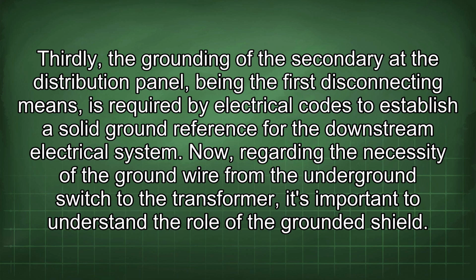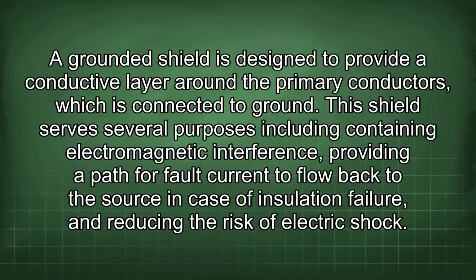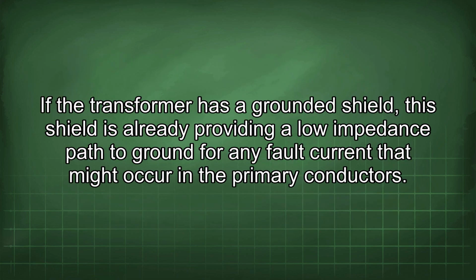Now, regarding the necessity of the ground wire from the underground switch to the transformer, it's important to understand the role of the grounded shield. A grounded shield is designed to provide a conductive layer around the primary conductors, which is connected to ground. This shield serves several purposes, including containing electromagnetic interference, providing a path for fault current to flow back to the source in case of insulation failure, and reducing the risk of electric shock. If the transformer has a grounded shield, this shield is already providing a low impedance path to ground for any fault current that might occur in the primary conductors.